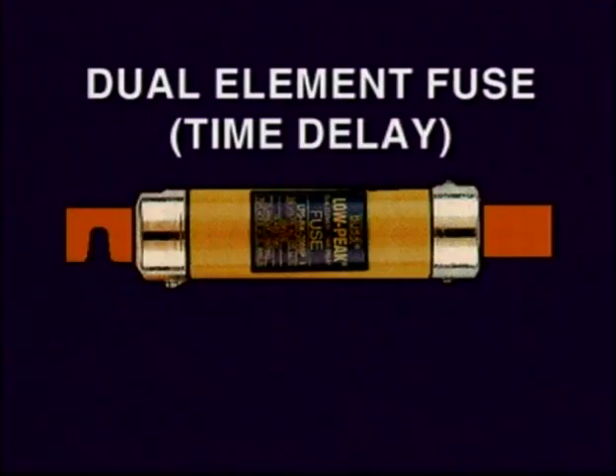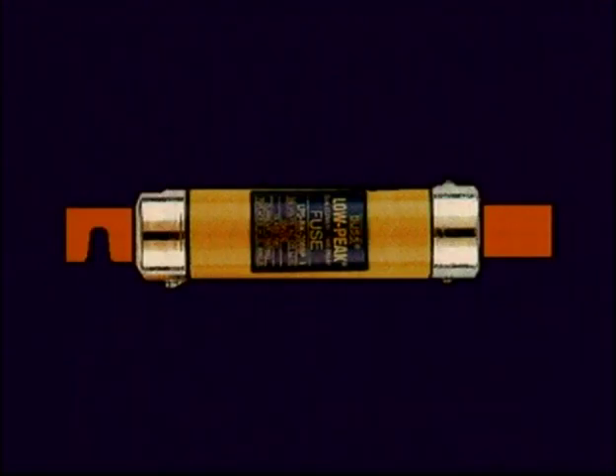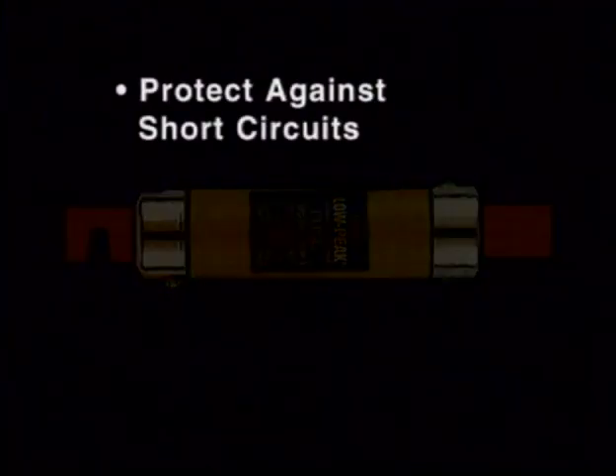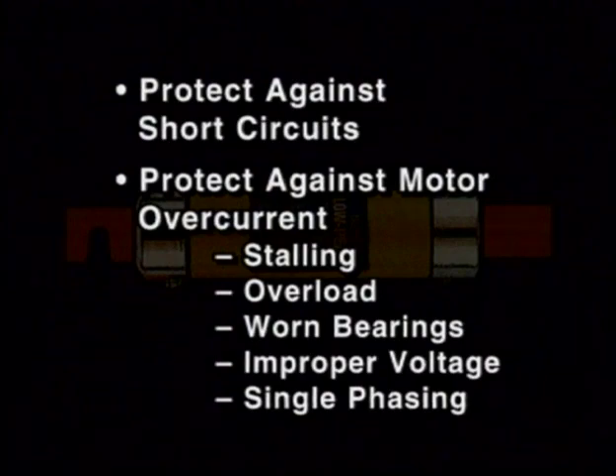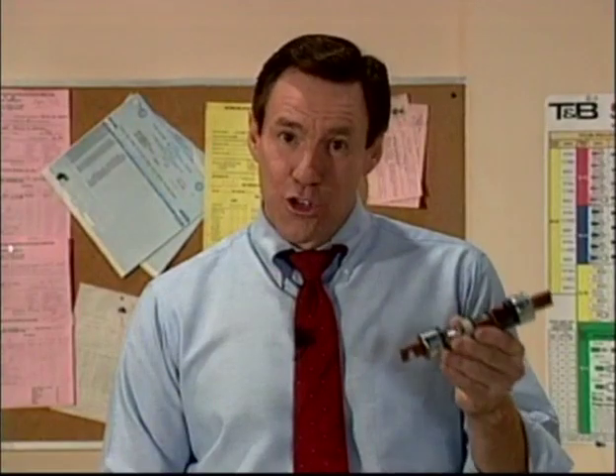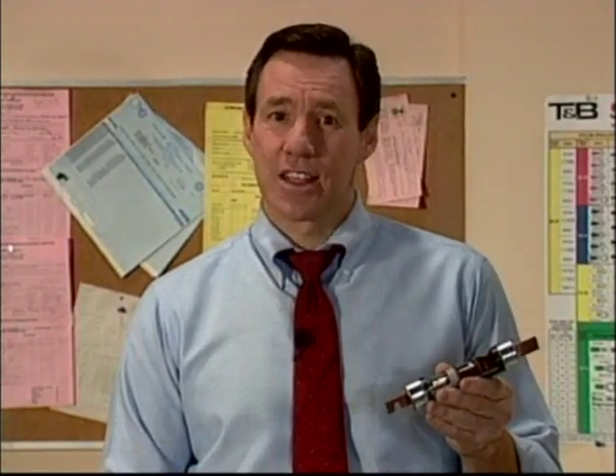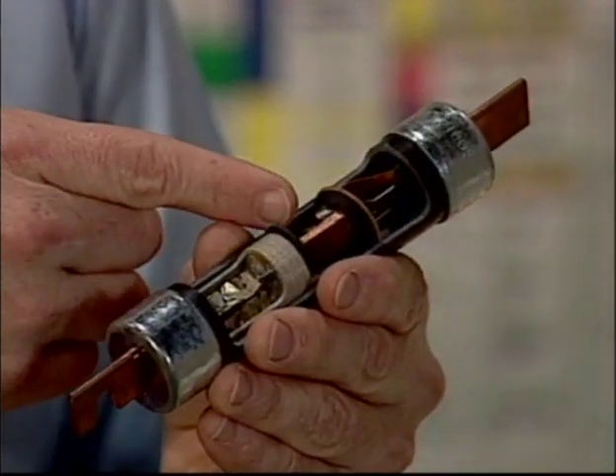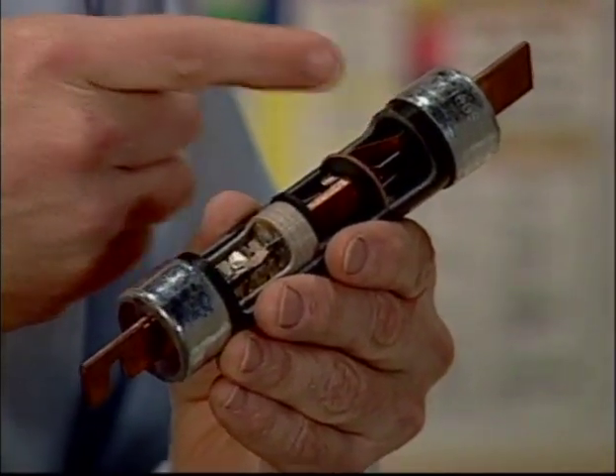To protect conductors and circuits from short-circuit and ground faults, we can also use dual-element time delay fuses. These fuses offer an additional feature of not only protecting against short circuits, but also they can protect motors from overcurrents due to stalling, overload, worn bearing, improper voltage, single phasing, and other possible causes. The dual-element time delay fuse works like this. It has 2 distinct overloads and short-circuit elements built in.